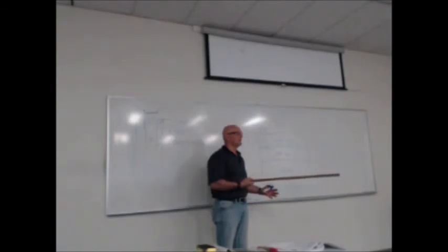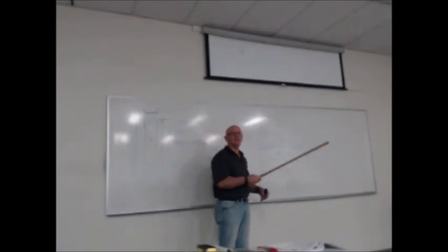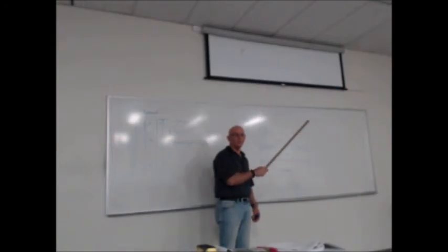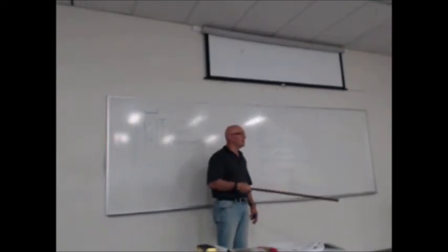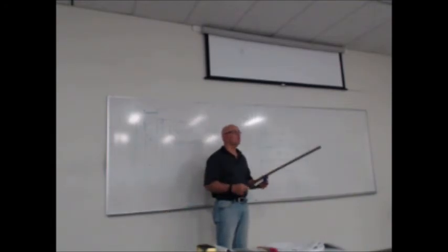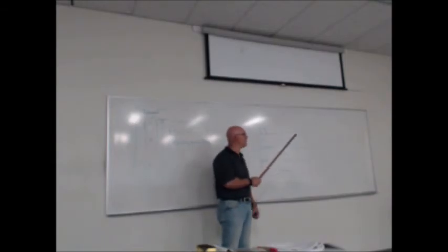I've had people in the past say, let's just do the ductwork on the roof. You can't do it. You've got all these penetrations going through the roof. Over a period of time it's going to leak because you're getting movement in the roof. You're relying on silicone. Not good practice. So to me, the minimum amount of penetrations going through there.